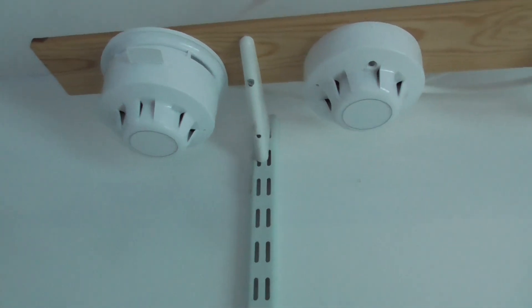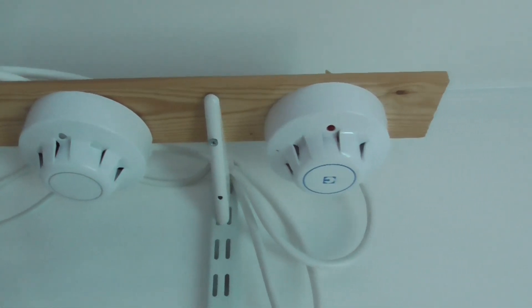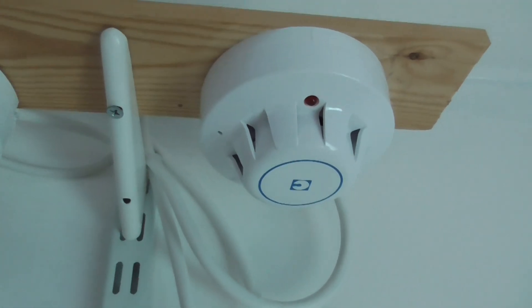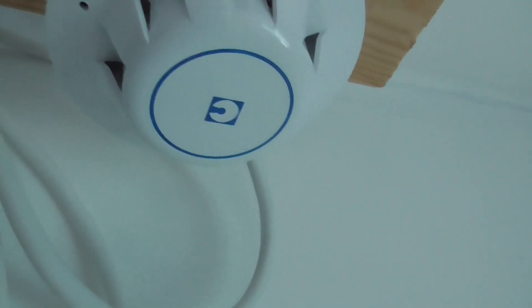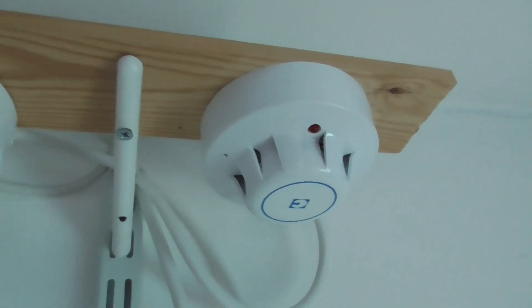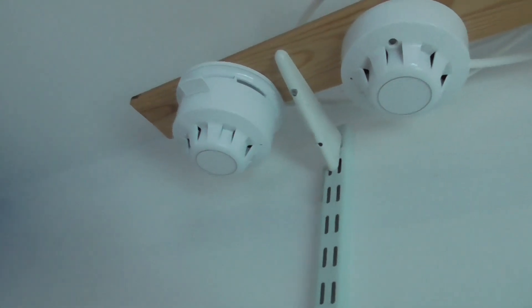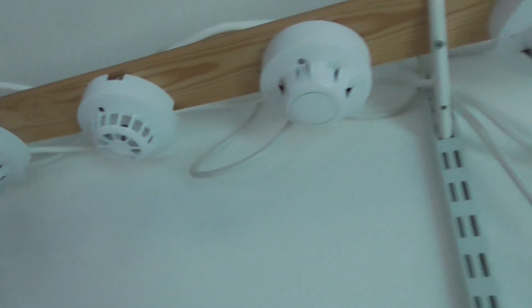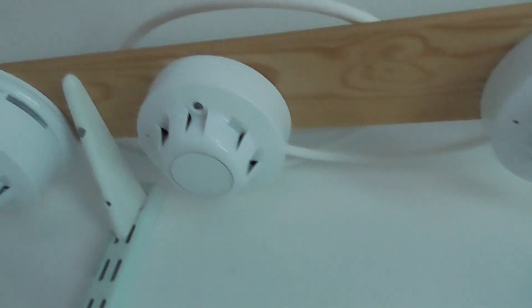This is a discovery sounder base, which is pretty cool — I've never had a discovery sounder before, and I do like these a lot. Then we've got a detector change: there used to be a beacon here and we now have an XP95 ionization detector which is Chubb-branded. It's an ionization detector — as you can see there's a red LED which means it's ionization. The beacon is just over here now, added onto the system on the shelter. The discovery sounder base is on a quieter volume and on the Apollo tone. We've also got two discovery detectors and an XP95 heat detector.